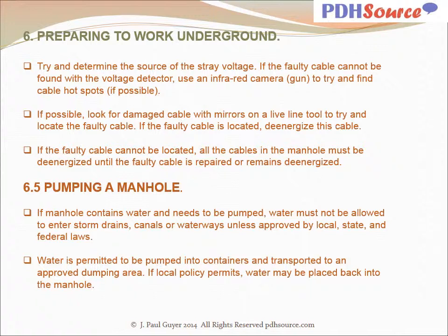If the faulty cable is located, de-energize this cable. If the faulty cable cannot be located, all the cables in the manhole must be de-energized until the faulty cable is repaired or remains de-energized. When pumping a manhole, if a manhole contains water and needs to be pumped, water must not be allowed to enter storm drains, canals, or waterways unless approved by local, state, and federal laws. Water is permitted to be pumped into containers and transported to an approved dumping area. If local policy permits, water may be placed back into the manhole.